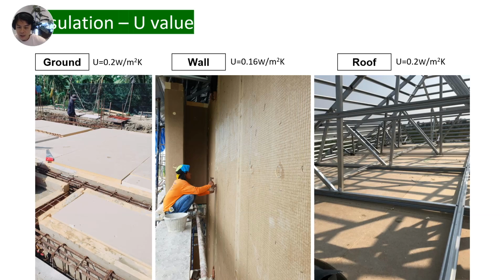Third, target U value for passive house. In passive house design, the recommended U value for the thermal envelope is below 0.15 watts per square meter K. But in Thailand, the temperature differences between indoor and outdoor are smaller than in Europe, and the number of heating and cooling degree hours is also lower. So considering the budget, we allow for a slightly higher U value that still balances performance and cost. So you can see the ground U value, the wall U value, and the roof U value are slightly higher than the U value suggested in Europe.